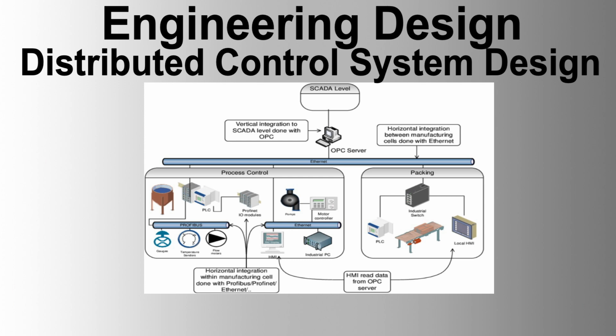5. The system will interface with a GPS clock to configure events and actions chronologically. The GPS clock will synchronize all external interfaces to within 0.01 seconds. 6. It must be possible to modify the DCS configuration online without stopping the processors or affecting existing configurations. Detailed procedures and time required for online configuration should be provided, highlighting any limitations.